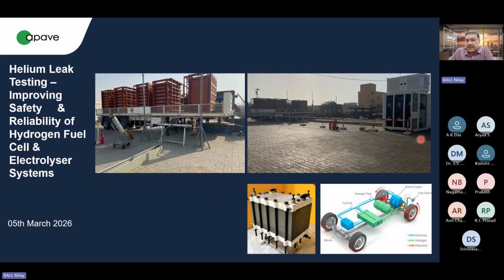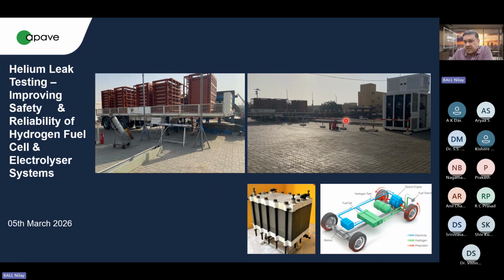Now, on the first night, I'm coming to this. Why I'm giving you this example and this storyline is where you need the fuel cell. Where do you need the helium leak testing? Now, when we first started the testing about 3 years back, we pressurized the whole system. We purged the system with gas, then nitrogen, and then hydrogen, and we sealed the system at 30 bar, and we left the site and went to the hotel.